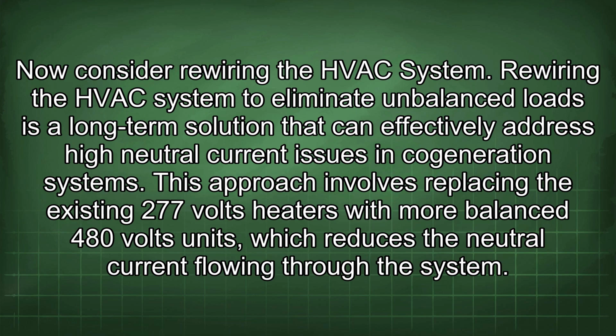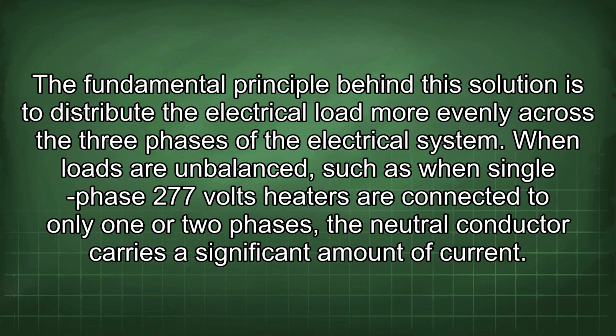Rewiring the HVAC system to eliminate unbalanced loads is a long-term solution that can effectively address high neutral current issues in cogeneration systems. This approach involves replacing the existing 277 volt heaters with more balanced 480 volt units, which reduces the neutral current flowing through the system. The fundamental principle behind this solution is to distribute the electrical load more evenly across the three phases of the electrical system. When loads are unbalanced, such as when single-phase 277 volt heaters are connected to only one or two phases, the neutral conductor carries a significant amount of current.